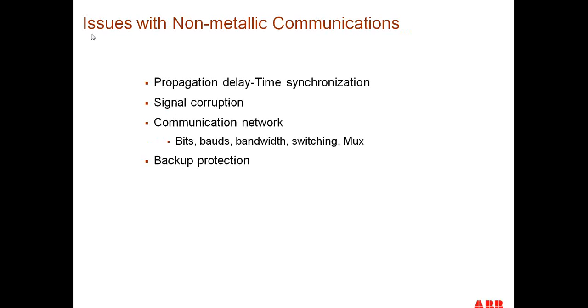When we go from using a metallic type twisted pair to a non-metallic type communications, being fiber or something, then there are a couple other things that we didn't have to worry about before. Now we need to worry about propagation delay time, propagation delay across the transmission line. We have to worry about time synchronization, so the samples at both ends of the line we're comparing apples to apples. We need to worry about signal corruption across the line. And we have to worry about communication networks, which means you have to worry about bits and baud and bandwidth and switching and multiplexing and all that other kind of stuff.